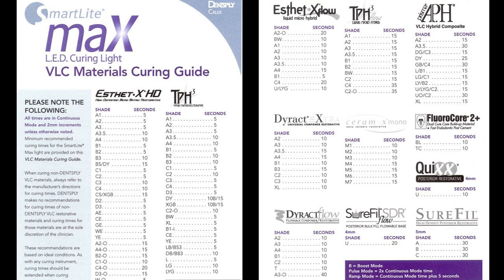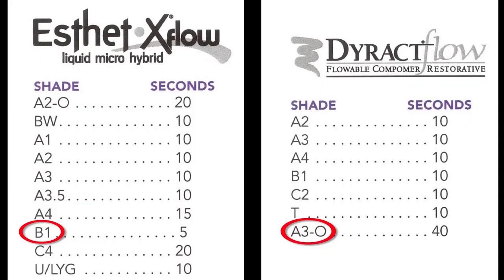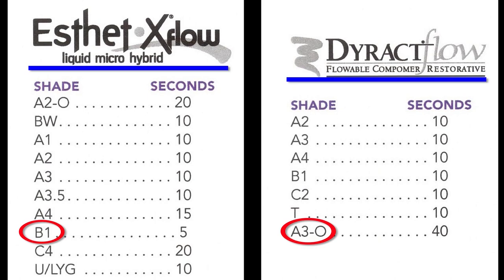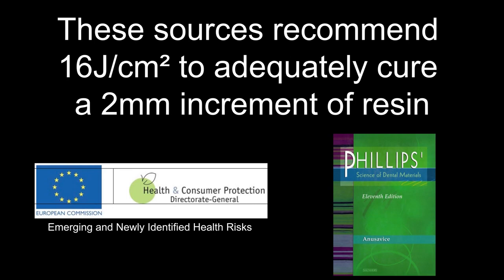Instructions for the SmartLight Max curing light recommend use between 5 and 40 seconds depending on the shade and type of resin. According to Dentsply, this light delivers 1200 mW per centimeter squared, meaning dentists must deliver between 6 and 48 joules per centimeter squared depending on the resin. Alternative sources such as the Phillips textbook and the European Commission on emerging and newly identified health risks both recommend delivering 16 joules per centimeter squared to adequately cure a 2 mm increment of resin.